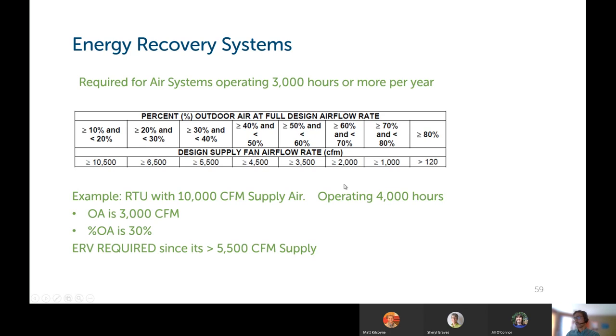This is a table from the code that has been updated for 2020. It's always been a little bit confusing to go through it, so I'll try to go through an example right now to see if that helps. My example is if you have a rooftop unit that has 10,000 CFM of supply air, it operates 4,000 hours a year, which is more than the required 3,000. This rooftop unit has 3,000 CFM of outdoor air. What you would do is you find what the percentage of outdoor air to supply air is. So that's 3,000 compared to 10,000. So that's 30% outdoor air.